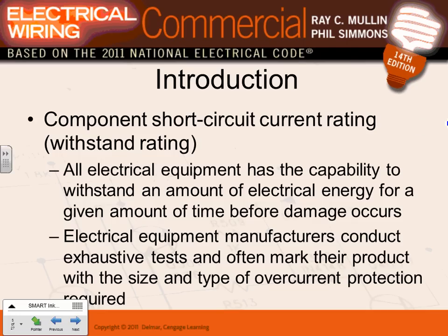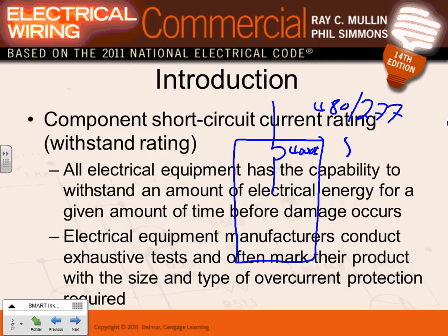Okay, so this is just a big fancy word to tell you that if you have a 4,000 amp switchgear, here's my 4,000 amp, 480/277, 85 kilo amp. That's a fancy word. I have a 4,000 amp switchgear, right? My switchgear, 4,000 amp, that's a continuous current that you can pull out of this circuit breaker, right? Now, the circuit breaker has an interrupting rating. Can you guys see 85,000 amp interrupting rating for the circuit breaker?